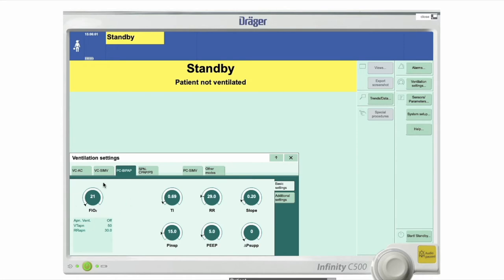And now you can examine the settings. So you've got settings all around here. These are the settings the ventilator feels the patient should have based on the weight you put in. What you'll notice are these little black triangles, and they will remain in place all the time, irrespective of the setting. So let's say I set this patient a pressure of 20. I'll increase it there to 22, confirm. That black triangle is there. So what that tells me when I look at the vent is we've set it at 22, but the ventilator suggests that this 15 is what should be normal for this child. And then you'll have that on each of the dials. So it's a nice little thing to remind you as to where you are in terms of ventilating this baby, and it's something that you may or may not find useful.